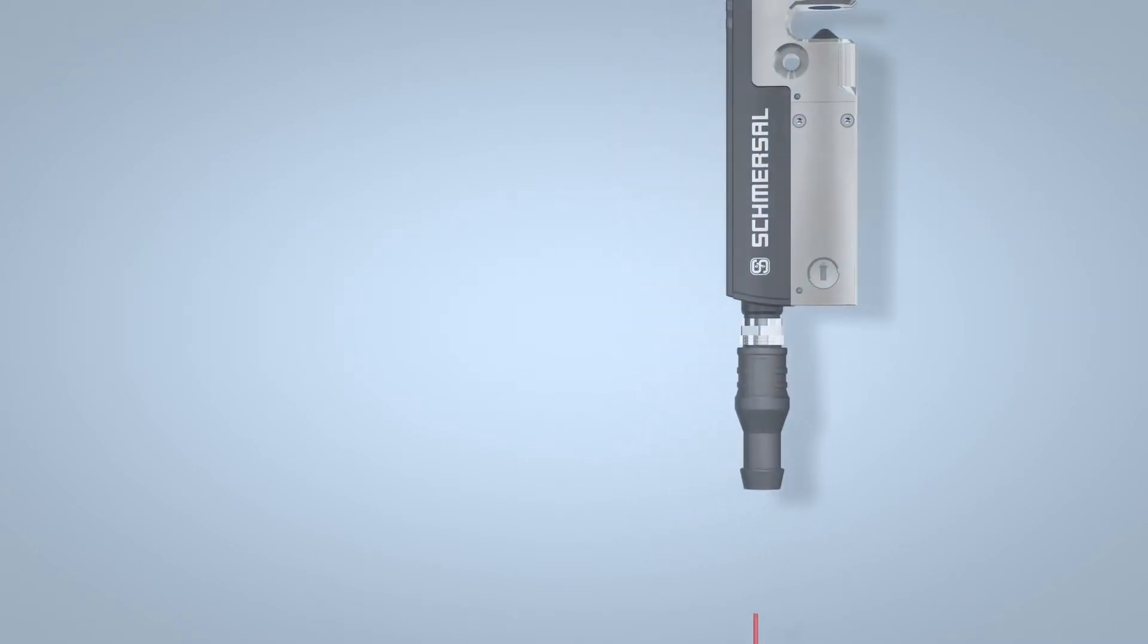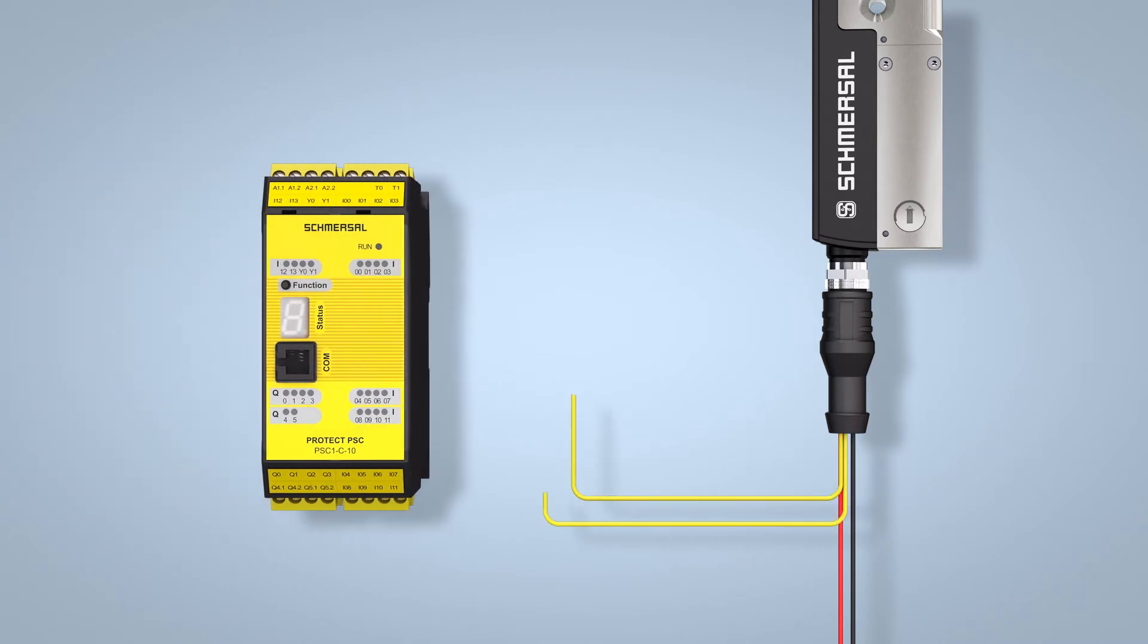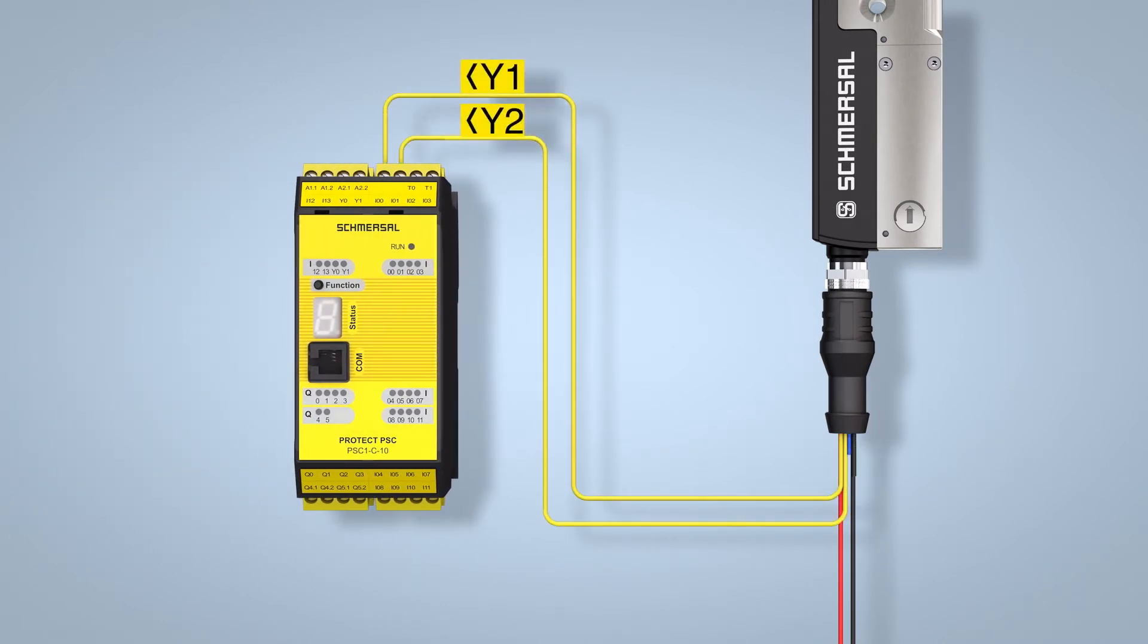Once the 24V supply voltage has been applied, the solenoid interlock makes two safety outputs available for connection to a safety monitoring module as well as a diagnostic signal for a PLC. The solenoid interlock is unlocked by activating the bistable magnet. If the solenoid is not actuated, the system remains in the locked state.